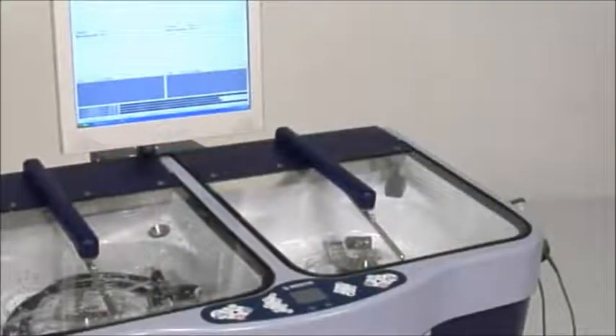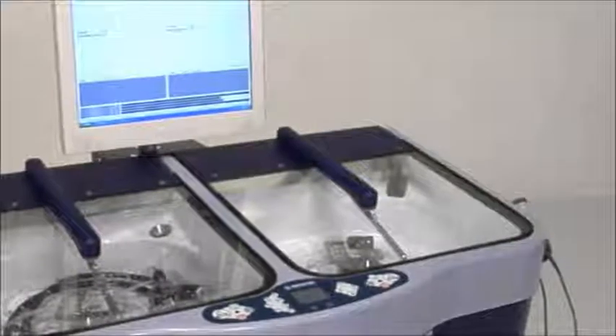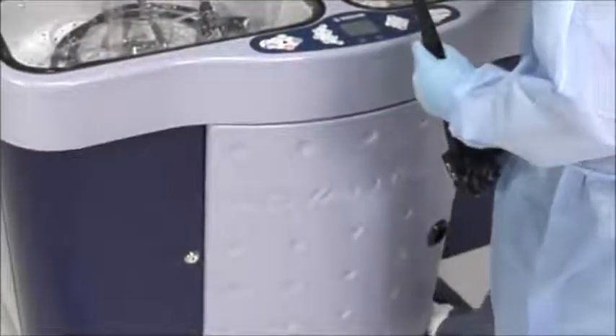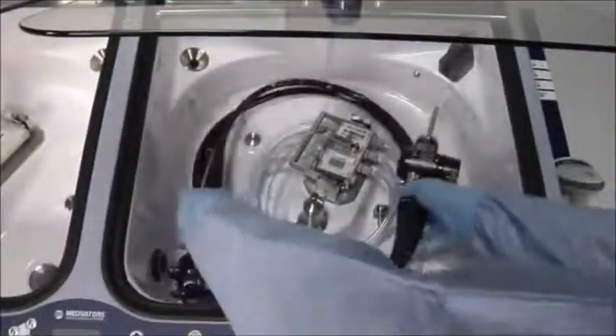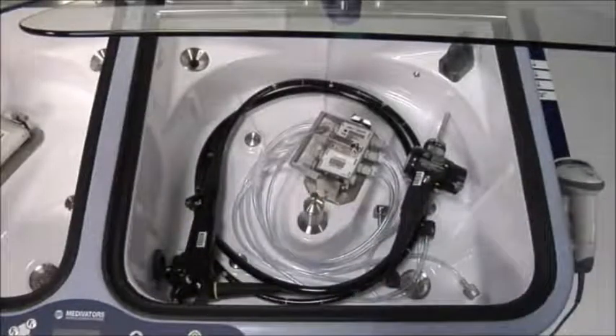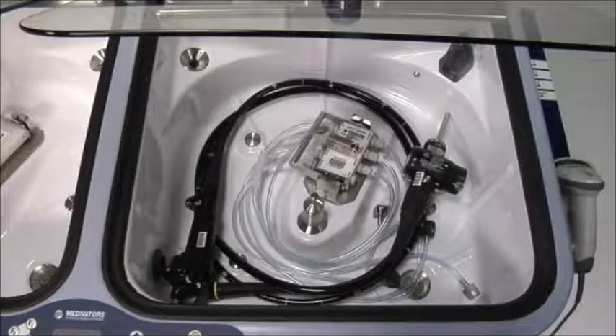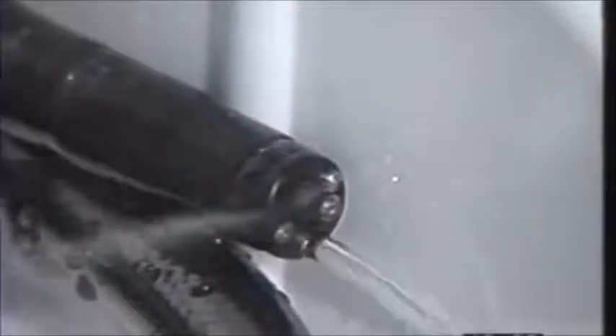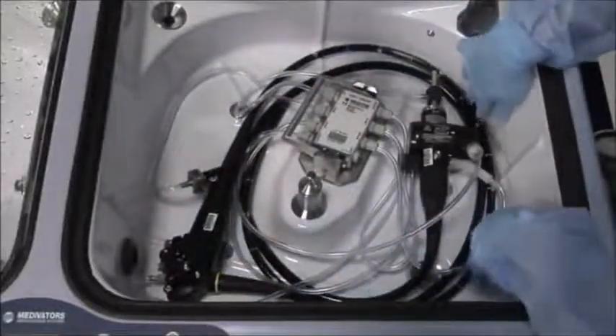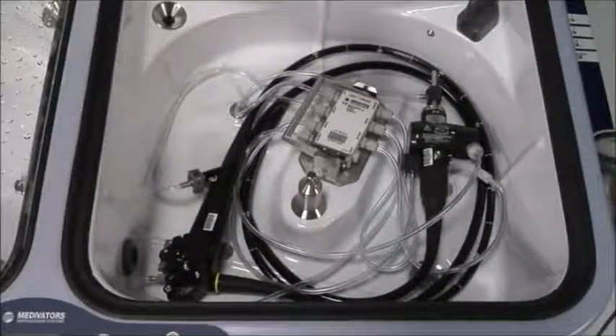Pre-coil the endoscope before placing it inside the basin. Hold the endoscope by the control section. Press the foot switch to open the basin lid. Put the endoscope in the basin. Place the control section in the lower left corner of the basin and the light guide connector at the right middle. The distal end should be positioned so that fluids passing through it into the basin will be clearly visible. The distal end needs to be tucked under the scope to ensure that water or disinfectant doesn't shoot up onto the lid. Hookup connector tubing should also be positioned so that it does not raise and become caught in the spray arm or spray head and does not cover the barcode.